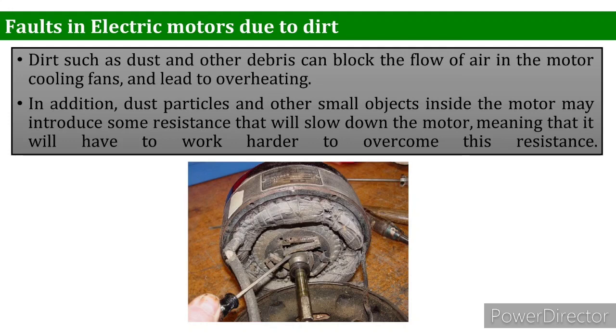Dirt is also an important environmental condition. Dirt such as dust and other particles in the air, the cooling fans, and the HVAC system cause a lot of problems with dust in the motor. Dust particles and small objects, especially small pieces of iron which you cannot see easily, can cause serious problems. Again, timely inspections and overhauling of the motors can protect this equipment.